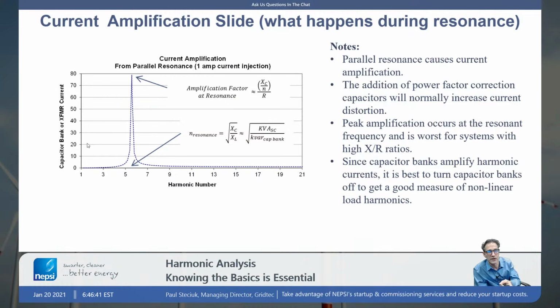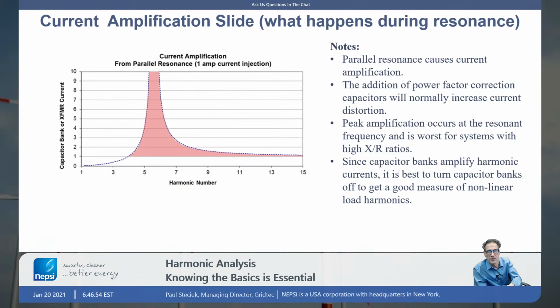So what I did here is, instead of developing an impedance curve, I developed a current amplification curve. It has the same look as the impedance curve, but we're doing current amplification. This will be the harmonic current injection amplified by this value within the resonant circuit. I'll show that in a moment. So you can see here that the current amplification is quite a bit and is over a wide range.